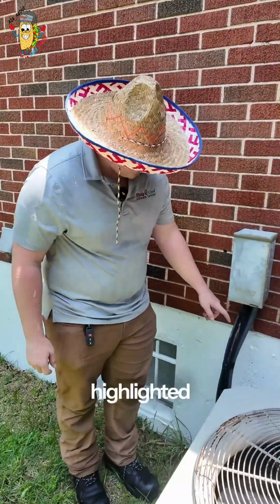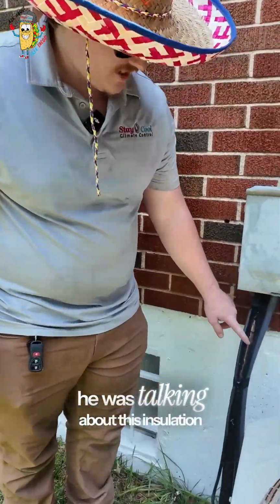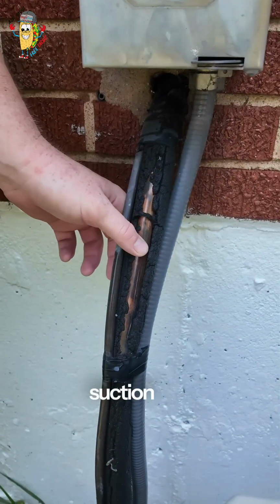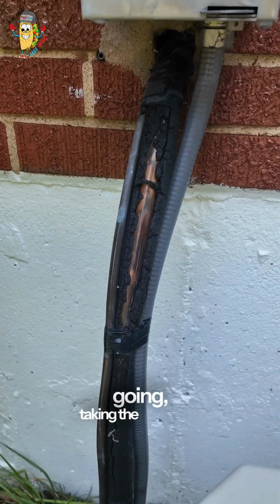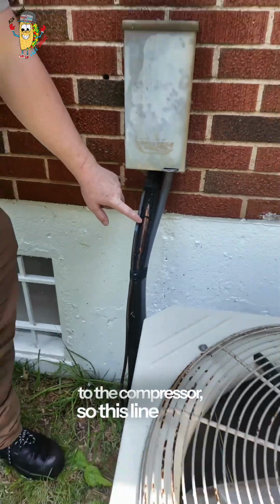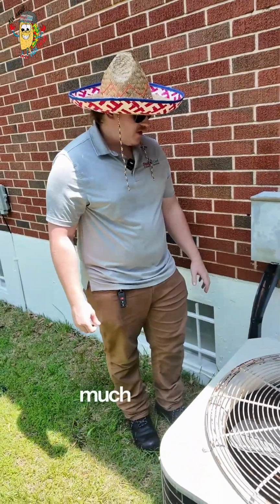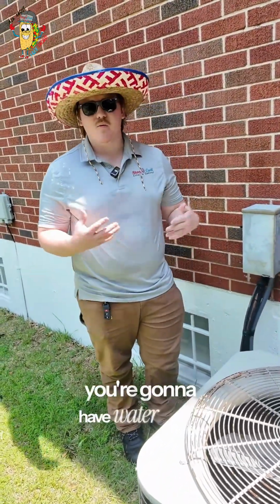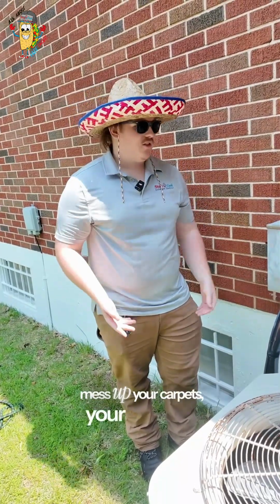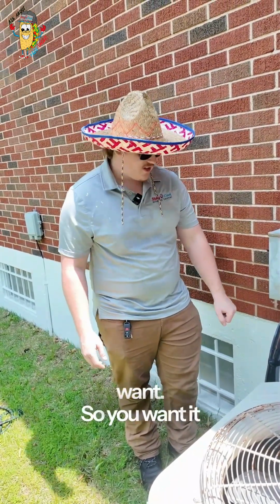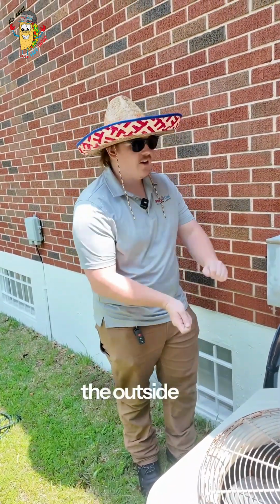So the last thing the inspector highlighted for us, he was talking about this insulation out here. It goes on the suction line, which is the line taking the refrigerant to the compressor. So this line often gets really cold. So pretty much if it's not insulated properly, you're gonna have water issues. Condensation will form on it. It can drip and mess up your carpets, your drywall, things you don't want. So you want it to be insulated completely from the outside all the way inside.